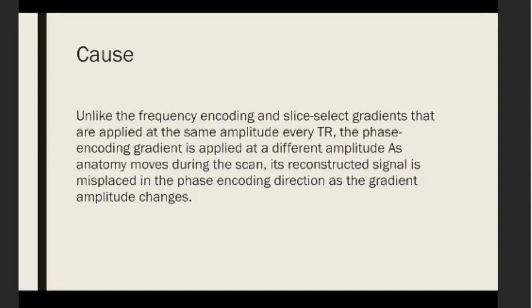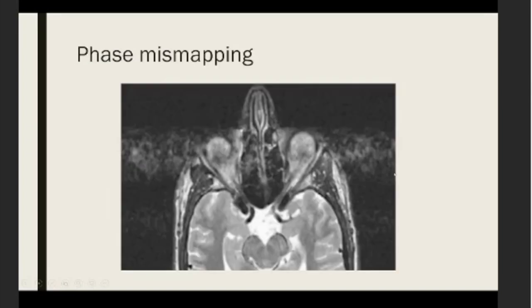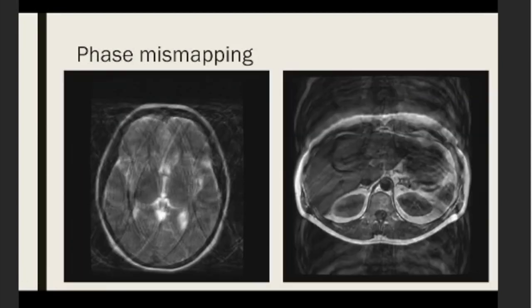Frequency encoding and slice select gradients are applied at the same amplitude every repetition time, but the phase encoding gradient is applied at a different amplitude. As anatomy moves during the scan, its reconstructed signal is misplaced in the phase encoding direction as the gradient amplitude changes. Examples include ghosting from a patient moving their eyes, from a patient tilting their head, and from respiratory motion or breathing.